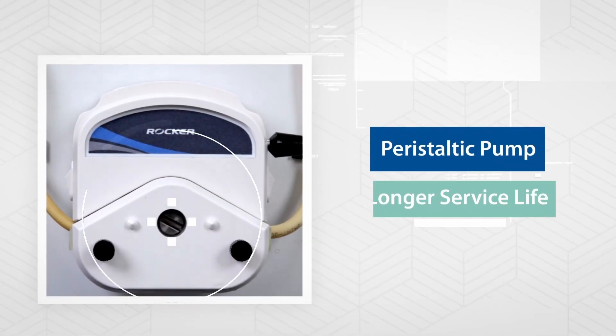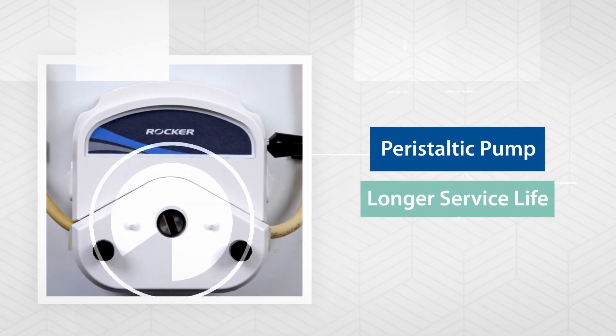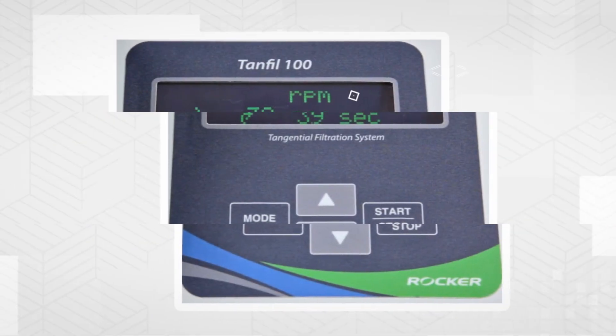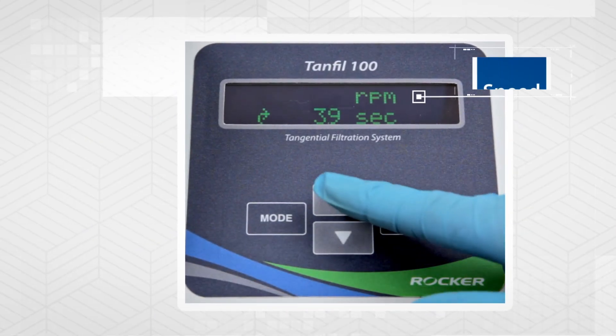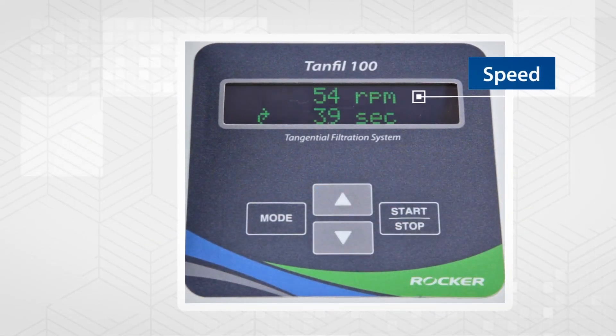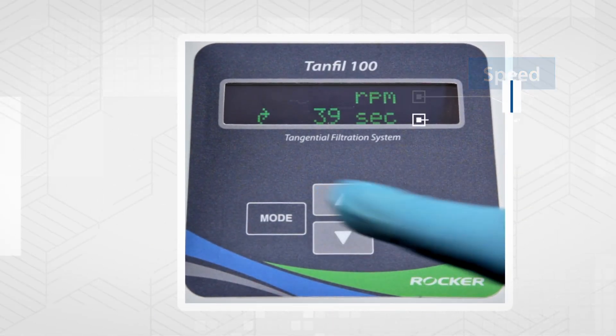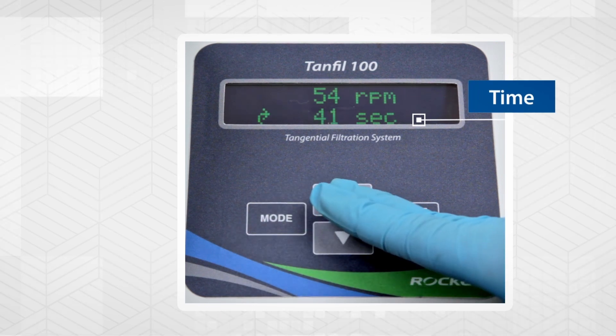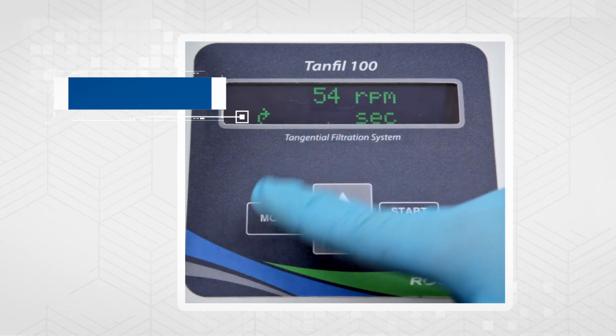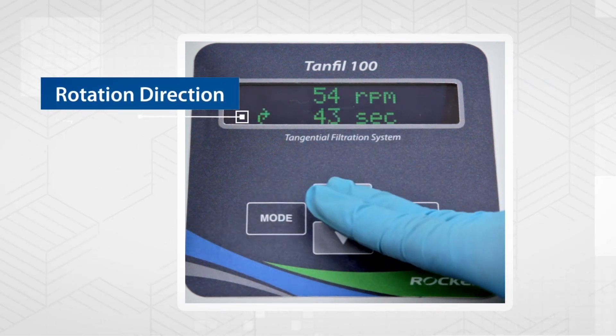It uses a peristaltic pump rather than a diaphragm pump to increase service life. Parameters in TANFIL 100 include speed, time, and rotation direction.